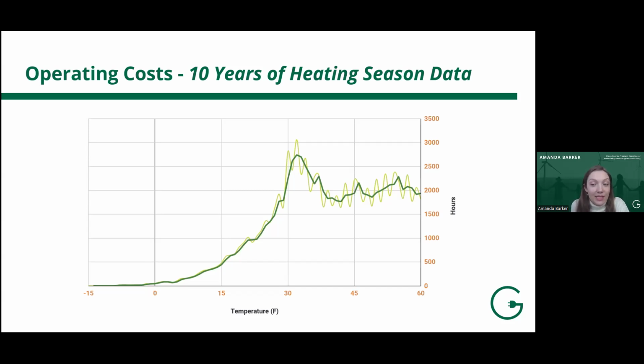Now, heat pumps do lose some efficiency below freezing, but modern cold climate heat pumps are still 100% efficient down to 0 degrees Fahrenheit, and they are still more efficient than the best gas boiler or furnace. And they continue to provide heat at 75 to 85% efficiency, all the way down to negative 17 degrees Fahrenheit. For some context, our area averages just 1 day a year when the mercury dips to 0 degrees Fahrenheit. So fortunately for us, we spend about 70 to 80% of our heating season above freezing temperatures. And so this isn't really a major concern for us.